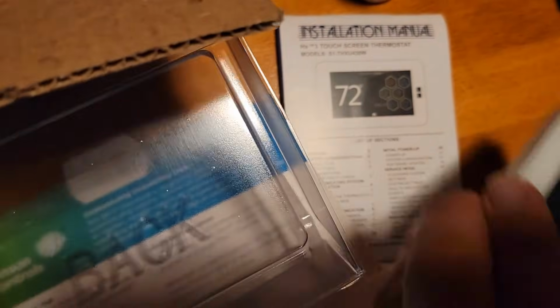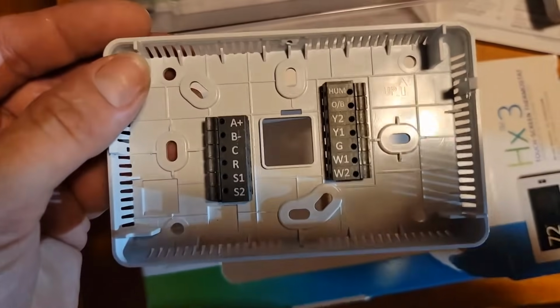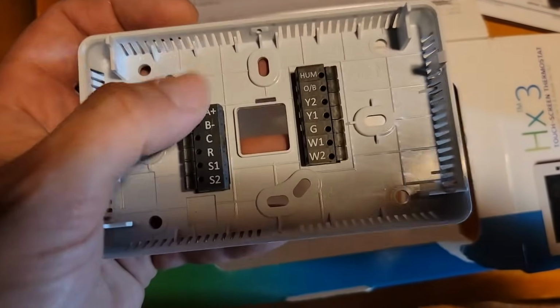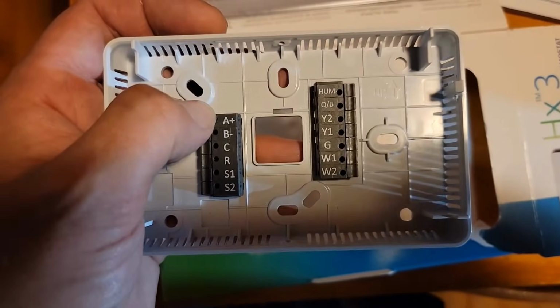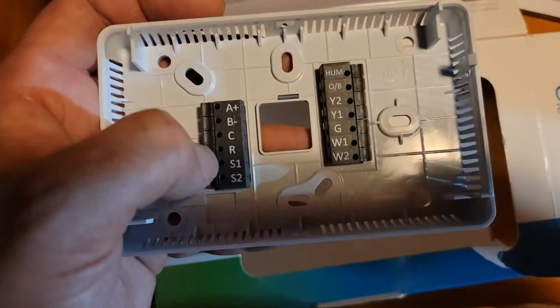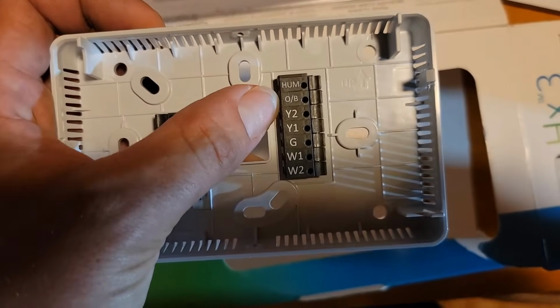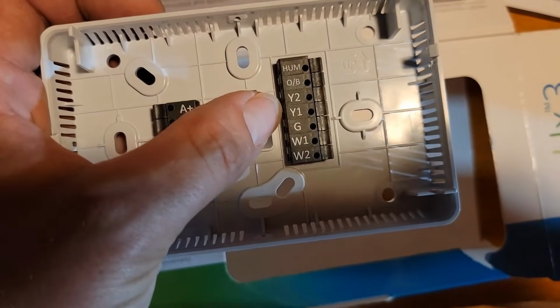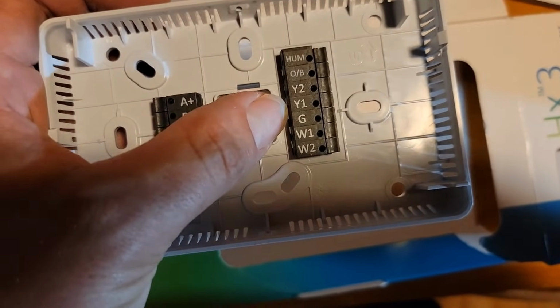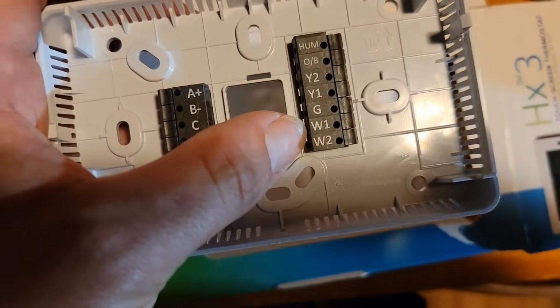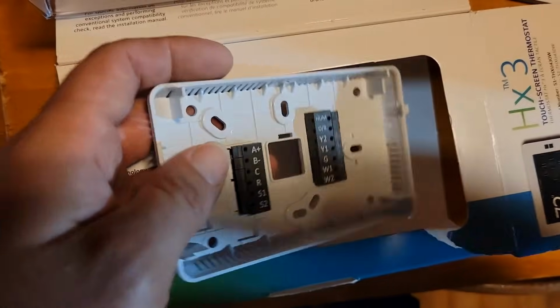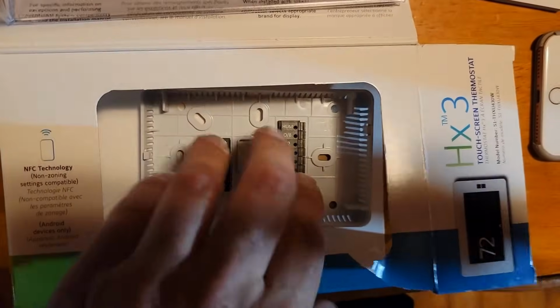There's the installation manual, which is very, very handy. And here is the mounting plate right here. You can see it can be communicating, which we're not going to use, the communicating A+, B-, C, and R. We're going to use the C and R, and then the reverse valve, second stage, first stage cooling, fan, and then first stage heating, second stage heating. We're going to hook this up conventional 24 volt wiring, not communicating.